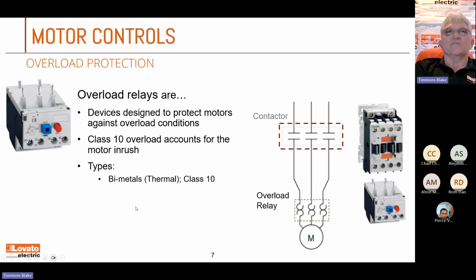Different types. You have some bimetal ones, and then you also have some electronic ones. So in the bimetal ones, they have the built-in thermal where it'll hold up to 10 seconds before it trips. But in these electronic classes, you got a little more control on this thing. You can do a real quick trip for some semiconductor devices you may not want to destroy. So you'll do a class 5. But you can see with electronic, we go up 10, 20, 30 seconds before it'll actually trip. A lot more control on an electronic. Actually, you're going to pay a little more for electronic overload.